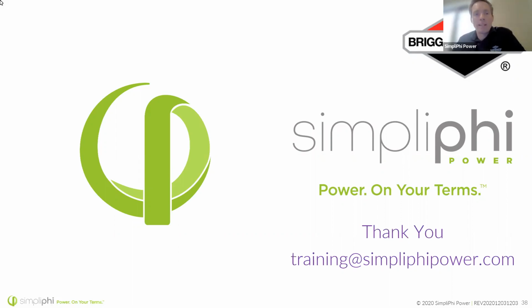We're in the process of getting our communications batteries to meet the communications protocol for their inverter, but until our BMS can talk to their inverter, I can't recommend using SimpliPhi batteries with Schneider yet. You can use Phi batteries as long as you program those set points in with Schneider, and that's what we sell. We actually sell Schneider inverters with our Phi batteries as part of our Access plug and play package.